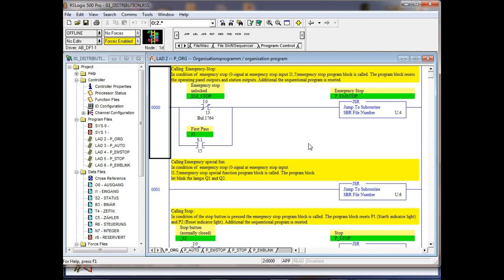So to create a comment, all you have to do is go onto the rung, right click on it, and select edit comment. And it'll pop another box up there. And you can do what? You can type in whatever comment you want. And I don't know any limit. RSLogix Pro limits you to one line, but RSLogix, as far as I can tell, doesn't. I haven't hit the limit yet. This is the label for this. So this, you can't tell it, but they're two different colors, yellow. And of course, this is the symbol bank, right? So you can give it... it's not a comment, they call it a label.